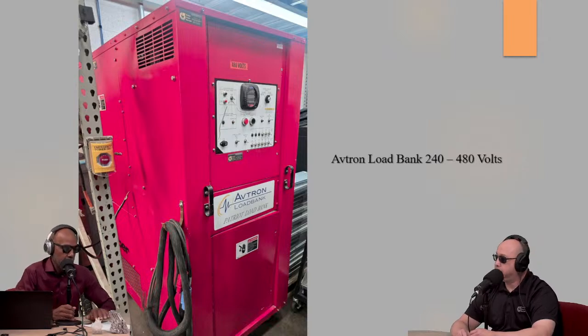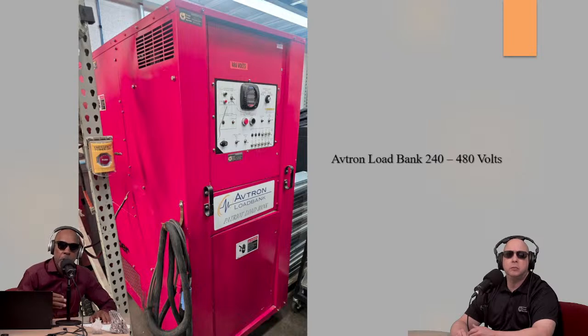A couple key things: the controlled environment. The load bank allows us to adjust the load, put different percentages of load on the system in a controlled environment versus doing it in the field. Do they do it in the field? Sure, this is a service our account managers can sell - load banking. If a customer wants to test their UPS, we can provide a load bank and do that for them.